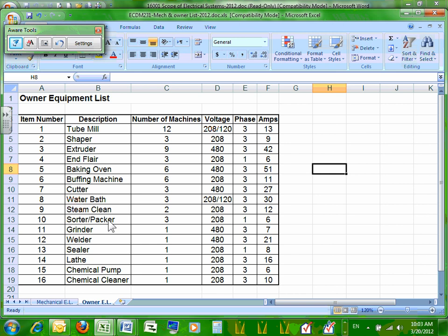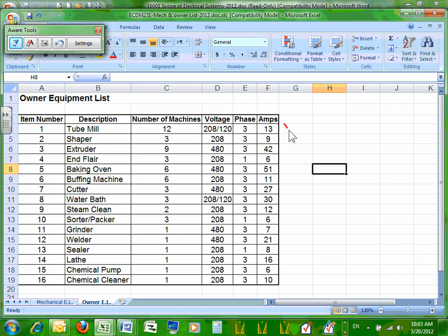Any questions? I think we've given the boxes a number, and that's what we're expecting as a power drop to that piece of equipment with an appropriate receptacle, and the equipment just kind of plugs in next to it. What we have done in the past, Guy told him, is to assume these are continuous loads and just multiply by 1.25 to size the overcurrent protection device and conductor. Yep, I think that's fair.